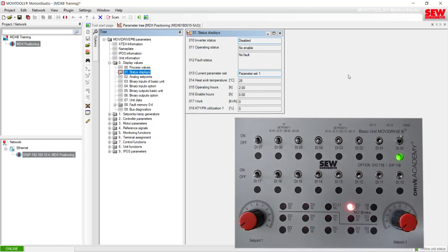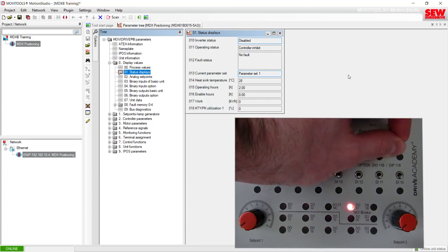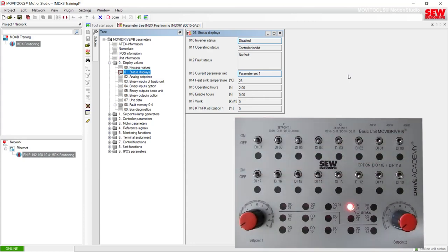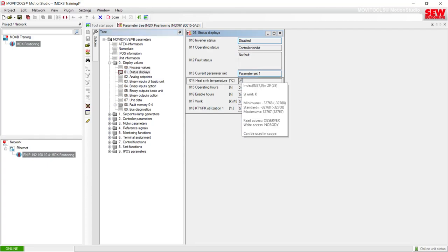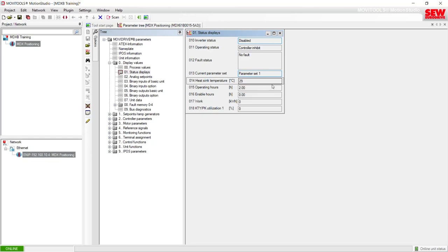I will flip DI00 back off. The next question in the lab instructions asks what is the inverter's temperature. The inverter's temperature is called the heat sink temperature — that's parameter 14, and it's currently at 29 degrees Celsius.